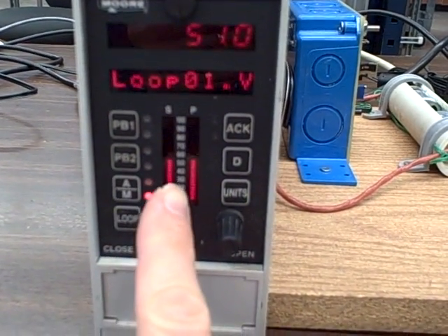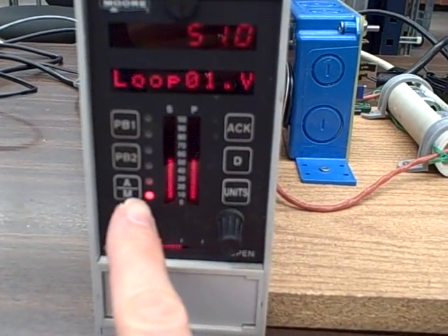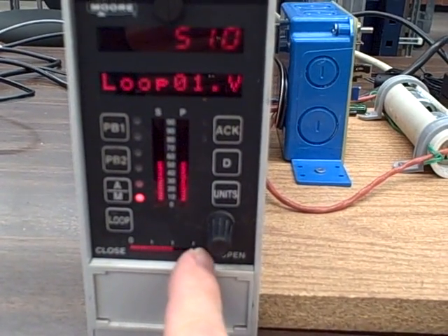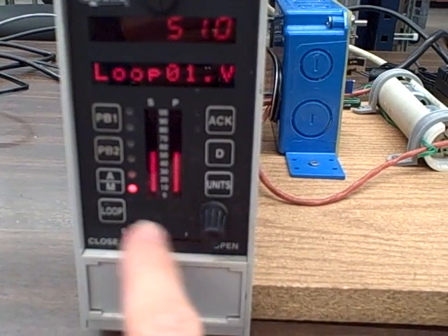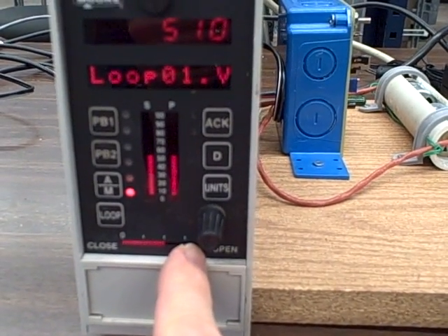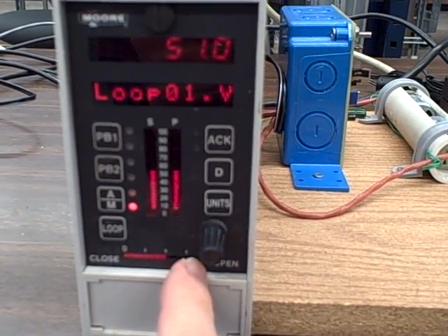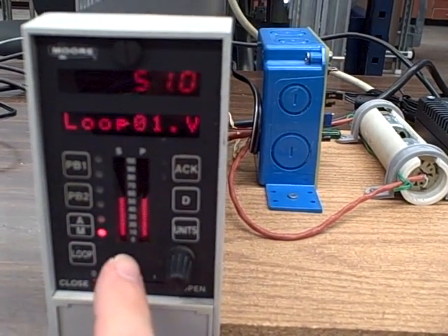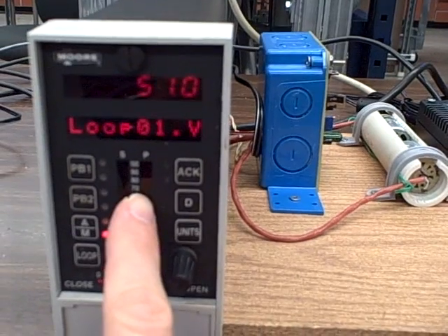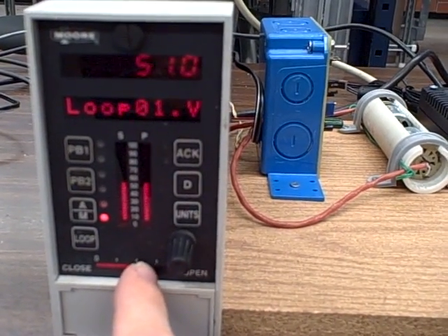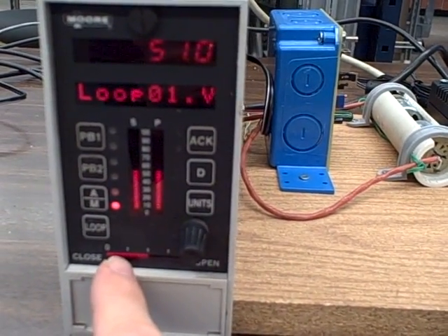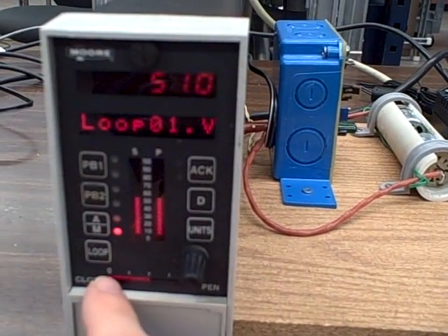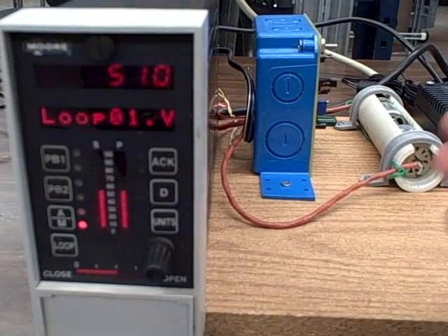Now remember what the controller tries to do. In automatic mode, if the controller sees a decreased motor speed, it tries to send more power to the motor to counteract that. But in this case, greater signal to the motor drive will actually cause the motor to slow down even more. Conversely, in automatic mode, if the controller sees a higher motor speed, its natural reaction is to cut power to the motor, to reduce power. But since we've now reversed the action of our variable speed drive, reducing that signal is actually going to cause the motor to go faster.